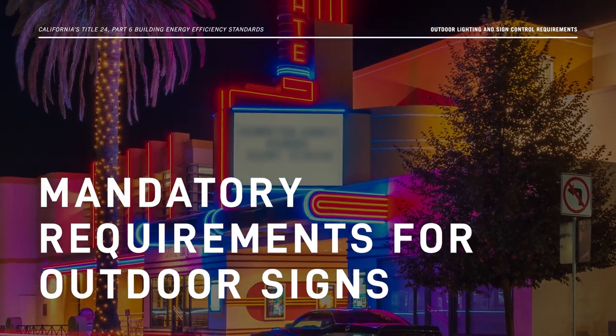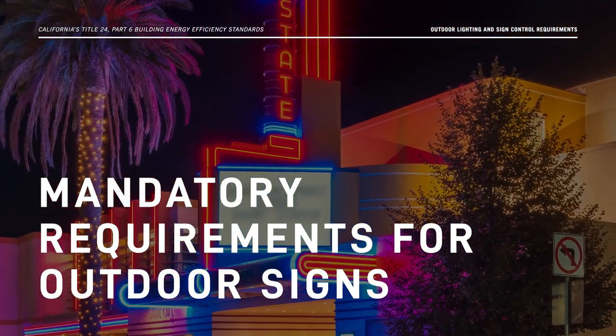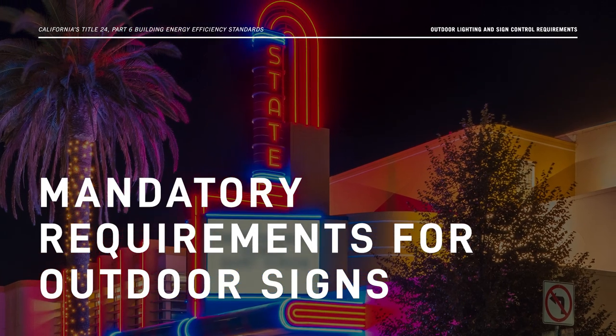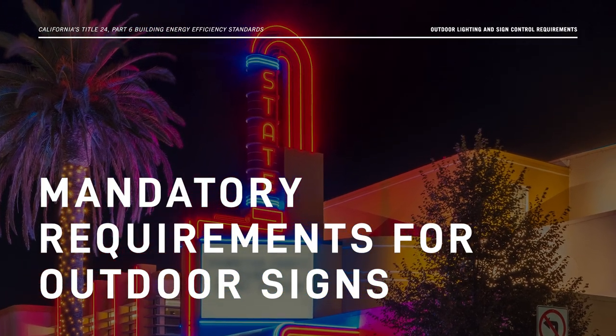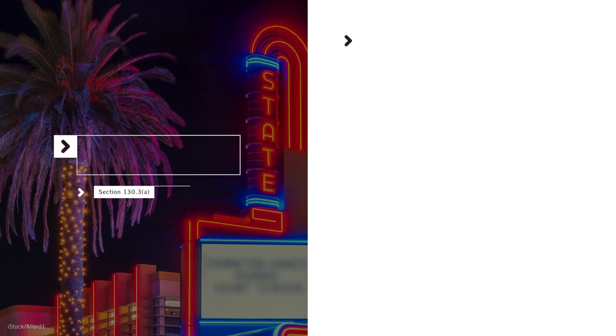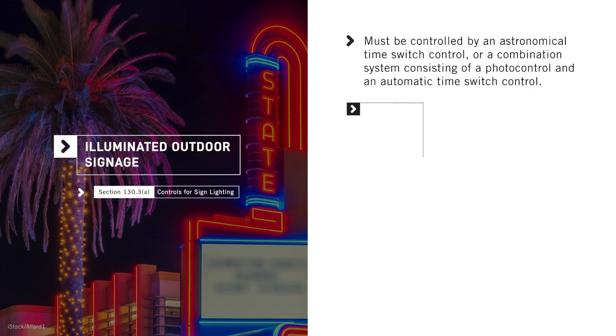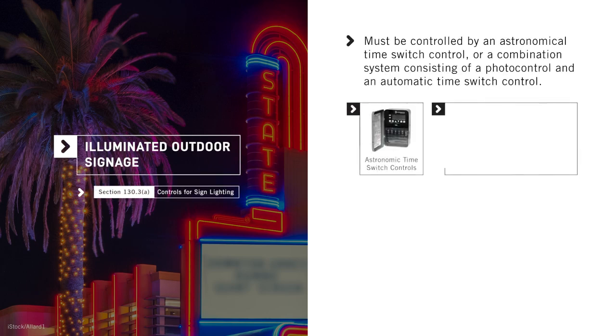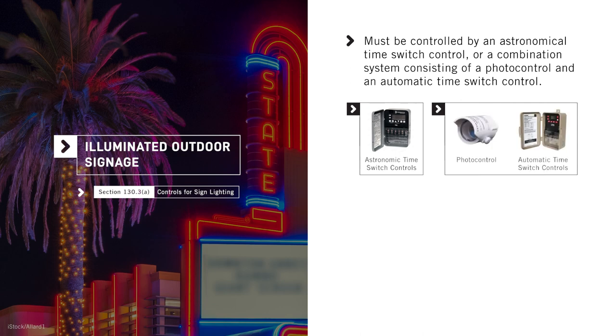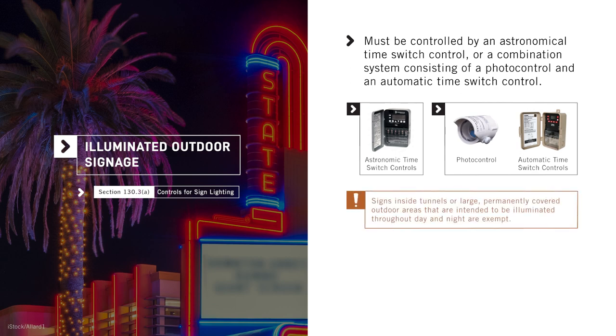Let's examine the control requirements for illuminated outdoor signs found in Energy Code Section 130.3. Illuminated outdoor signs must be controlled by an astronomical time switch control or a combination control system consisting of a photo control and an automatic time switch control. Signs inside tunnels or large, permanently covered outdoor areas that are intended to be illuminated throughout day and night are exempt.